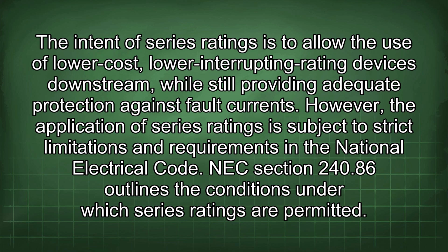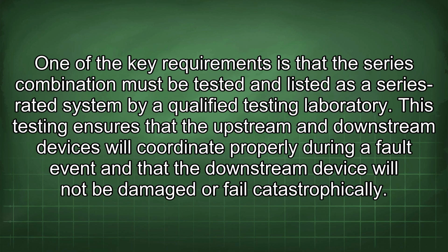However, the application of series ratings is subject to strict limitations and requirements in the National Electrical Code. NEC Section 240.86 outlines the conditions under which series ratings are permitted. One of the key requirements is that the series combination must be tested and listed as a series-rated system by a qualified testing laboratory. This testing ensures that the upstream and downstream devices will coordinate properly during a fault event and that the downstream device will not be damaged or fail catastrophically.